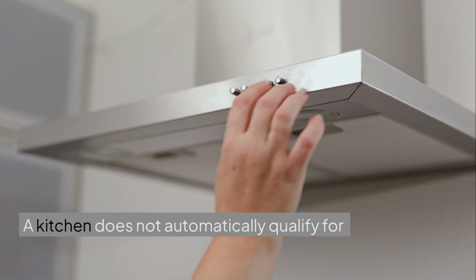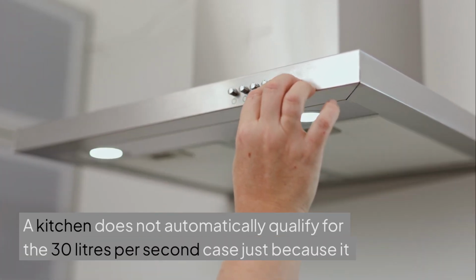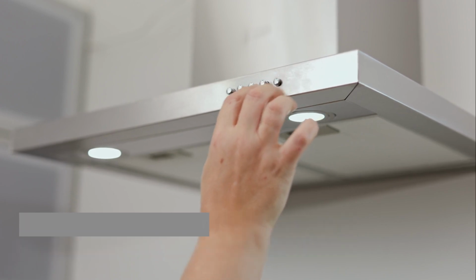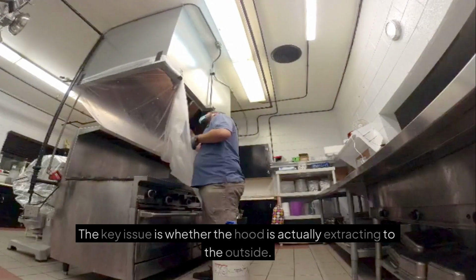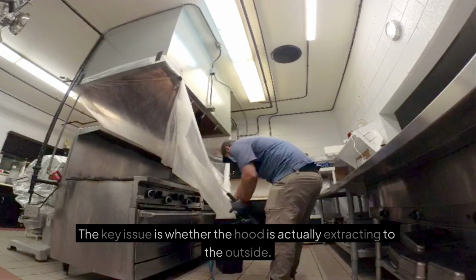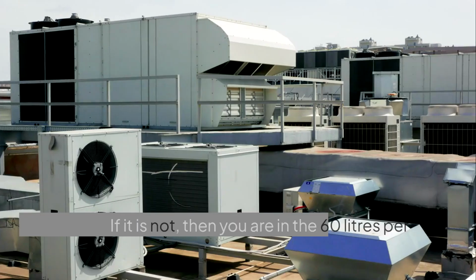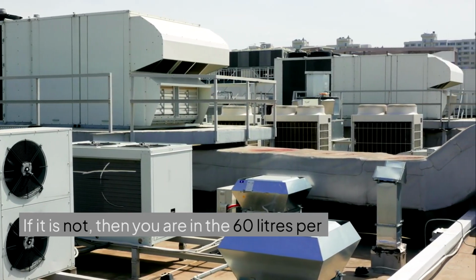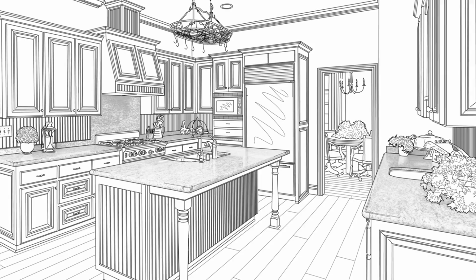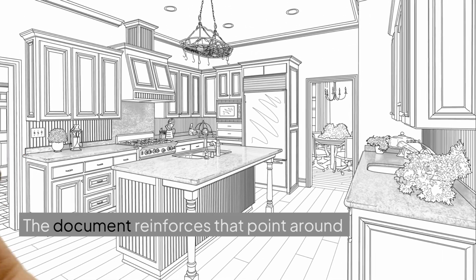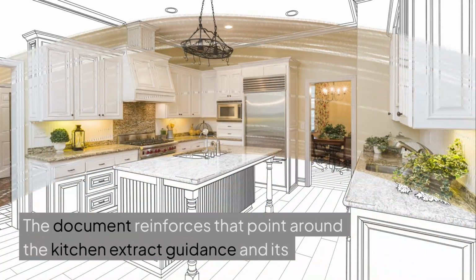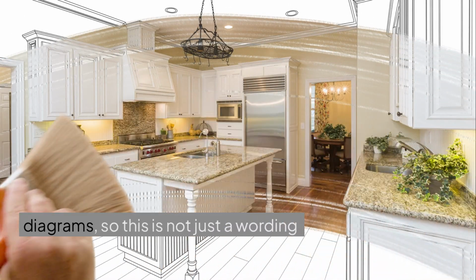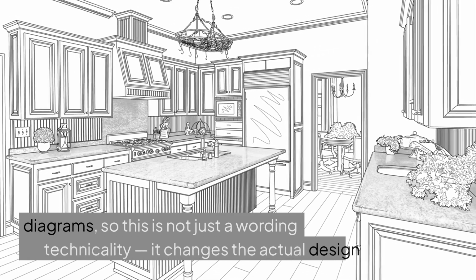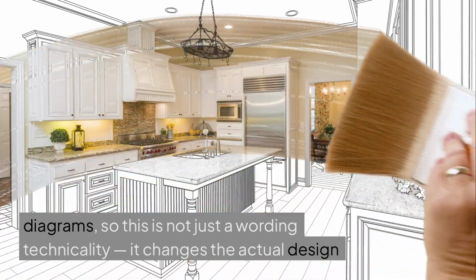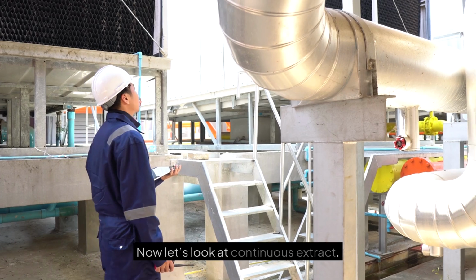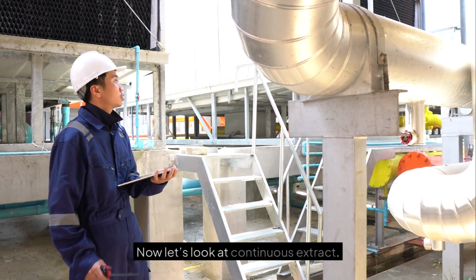A kitchen does not automatically qualify for the 30 litres per second case just because it has a hood over the hob. The key issue is whether the hood is actually extracting to the outside. If it is not, then you are in the 60 litres per second case. The document reinforces that point around the kitchen extract guidance and its diagrams, so this is not just a wording technicality, it changes the actual design requirement. Now let's look at continuous extract.